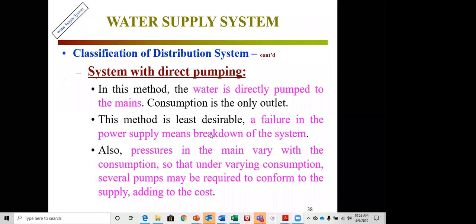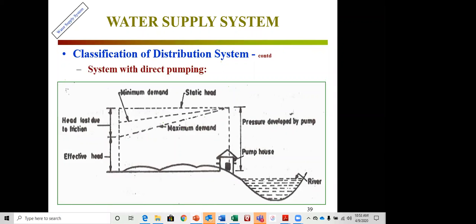In a direct pumping system, water is pumped directly to individual house mains. This is the least desirable method because failure of the power supply shuts down the entire system, and pressure in the mains varies with consumption. Under varying demand, several pumps may be required to conform to supply requirements, adding significantly to cost.